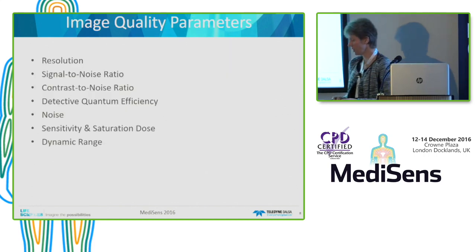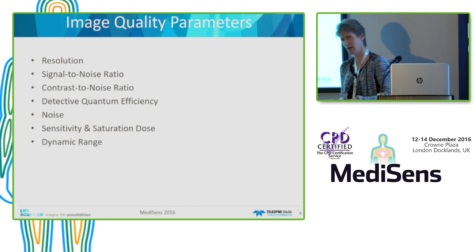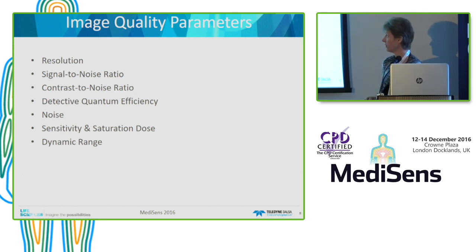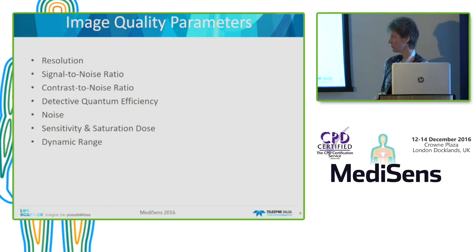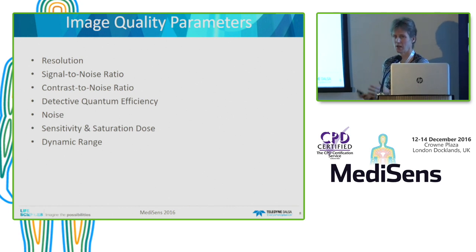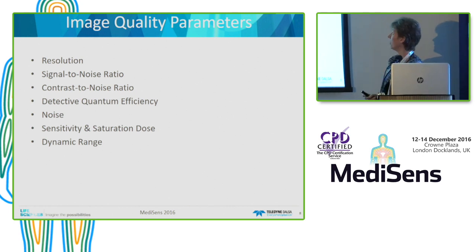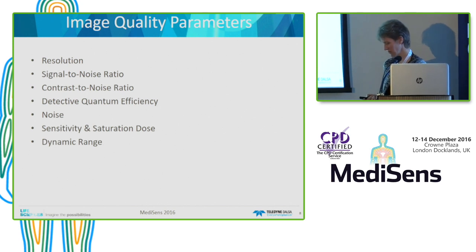So which parameters define image quality? It's the resolution, the signal-to-noise ratio, the contrast-to-noise ratio, DQE noise, sensitivity and saturation, dose, and dynamic range. I want to go through all of these aspects in this presentation. For me, the starting point is the x-ray detector — I'm focusing on what happens at the detector, not the total system, though the tube and system configuration also play a role in what you finally see in the x-ray image.